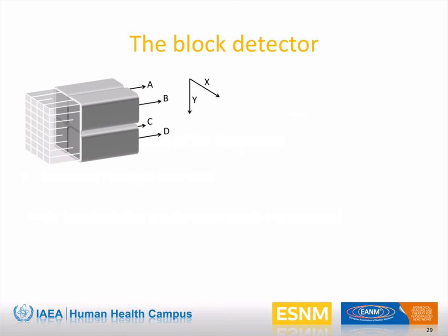The empty space between elements is filled with a white reflective material to optically separate them and to ensure the maximum efficiency in light transport toward the photodetector. The light emerging from the scintillator is sampled by 4 square single-channel PMTs arranged on a 2x2 matrix.